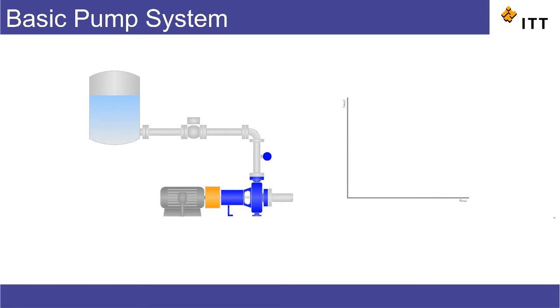There's a difference in elevation between the pump and the tank, so that makes up the static head which is shown by the constant green line on the flow versus head curve on the right. In addition, you've got the friction losses in the line which increase as the flow increases.